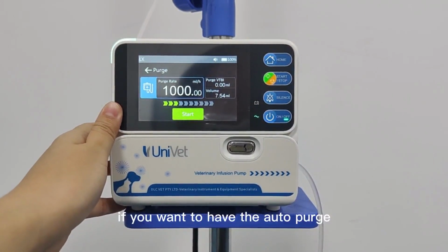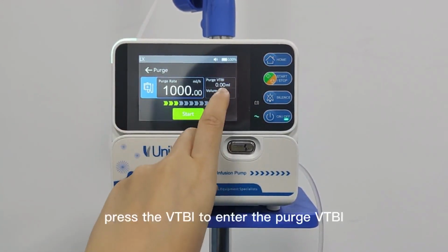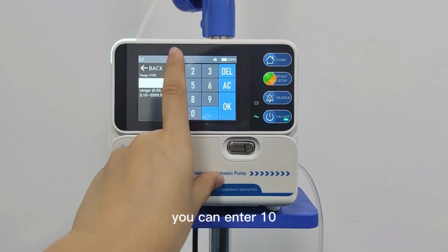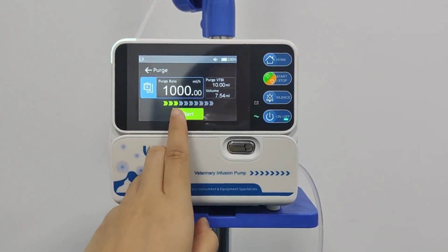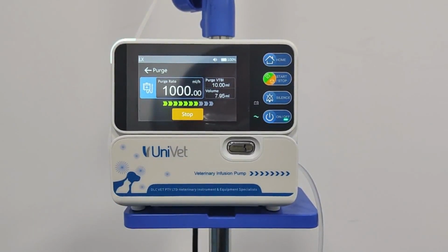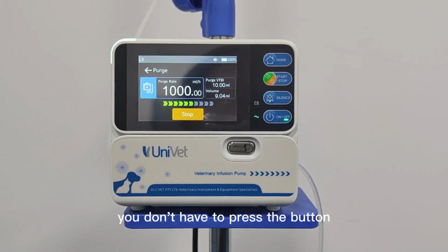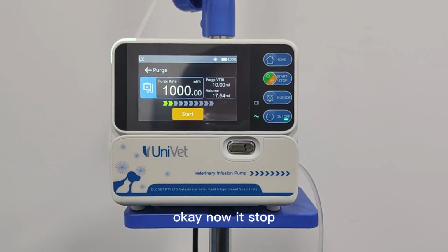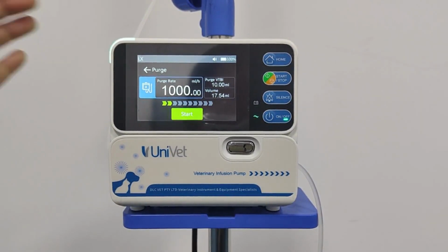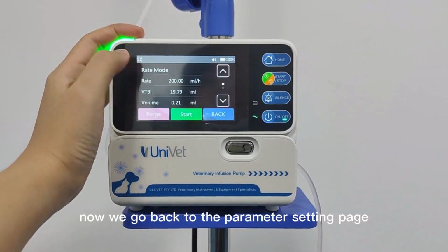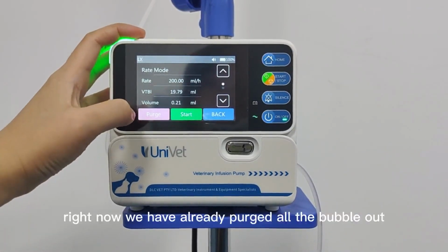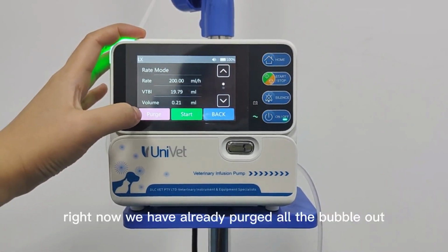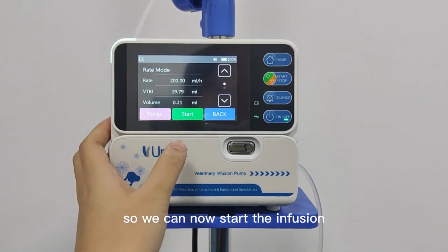If you want to have an auto purge, press the VTBI to enter the purge VTBI. You can enter 10 and click start. It will start the auto purge. You don't have to press the button. Okay, now it stopped. Now we go back to the parameter setting page. Right now we have already purged all the air bubbles out, so we can now start the infusion.